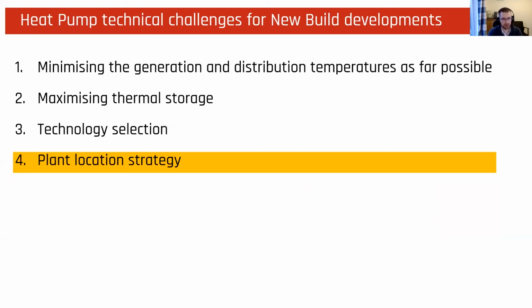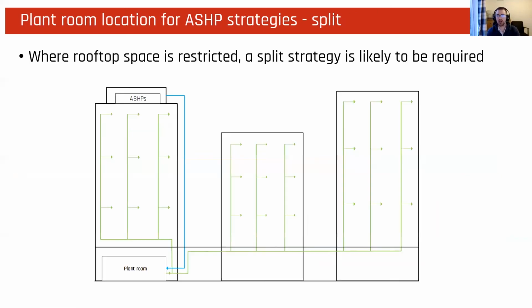So the last one, to be honest, probably the one that I've spent the most time being involved with, is plant location, and one that often gets rolled back a little bit, back to the drawing board. So for air source heat pumps, one of the options is to have a split strategy where the air source heat pumps are located on the roof, and we have thermal storage distribution, maybe some boilers at ground level, and then we distribute out from there. Where rooftop is relatively restricted, but there is some available for air source, that's probably likely to be the optimal strategy.